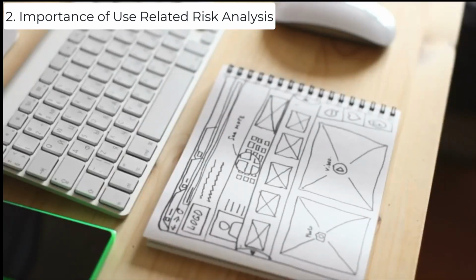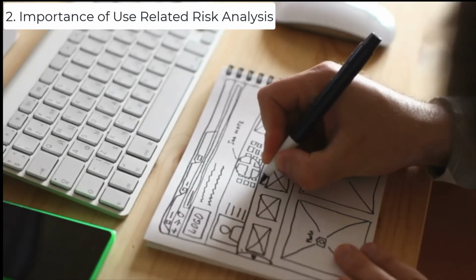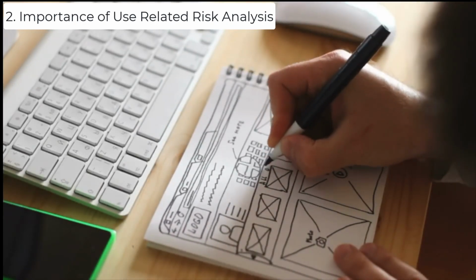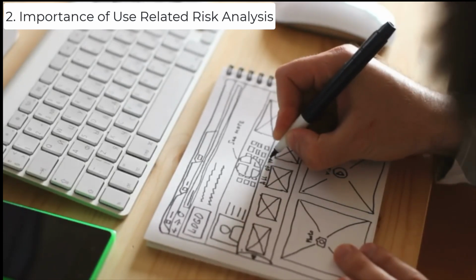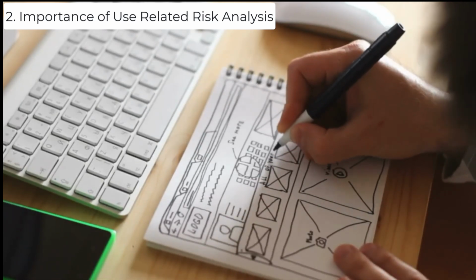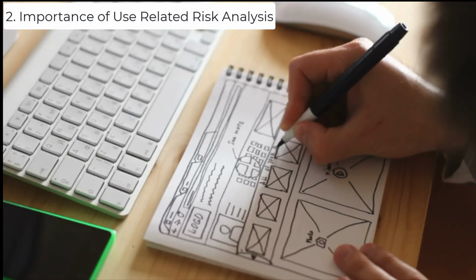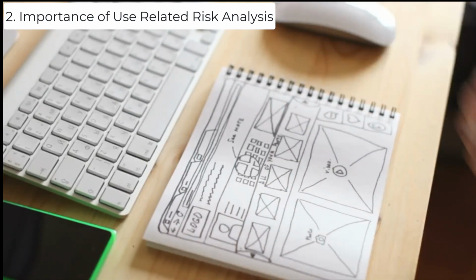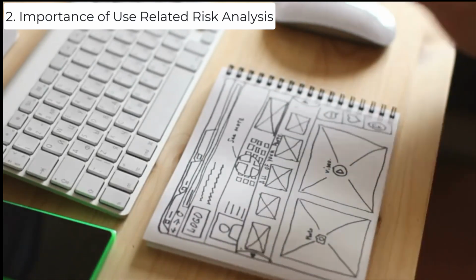When planning a combination product design change, consider all potential effects on the use-related risk analysis. Depending on how the changes affect use, an additional human factors validation study might be necessary, focusing at the very least on the combination product critical tasks impacted by the modification.